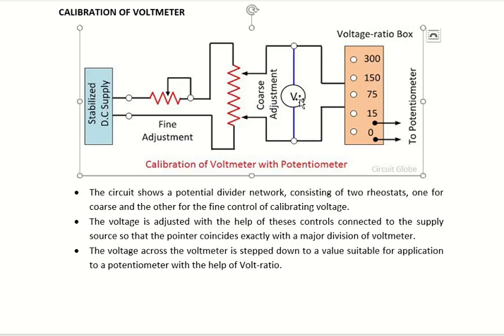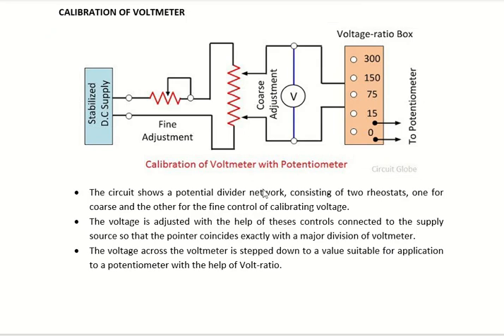Next we see the calibration of voltmeter. This is the circuit for calibration of voltmeter. You have a DC source and you measure its voltage using a potentiometer as well as a voltmeter. If both voltages are the same, the voltmeter is in good condition, or calibrated. Otherwise there is an error.